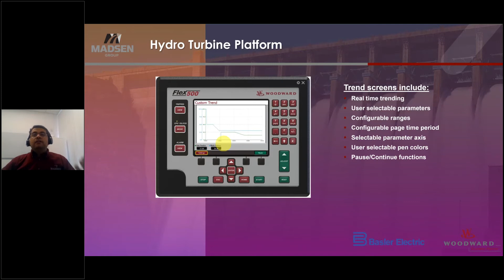It comes with timestamps for alarms and trips, so we pre-configure it. So every single alarm that the generator produces comes with a timestamp. It tells you when the alarm happened, at what time. And if you would like to synchronize your Flex500 with your PLC, we have an SNTP server built inside the unit itself. So the unit itself can connect to your SNTP server and synchronize the time, so that if a trip happens within the plant, the time on the Flex500 is similar to the time on the PLC, and that can help you with the diagnostic.